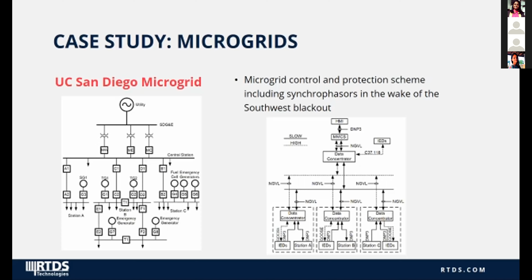On the left, you can see a diagram of the microgrid topology. You can see there are three utility ties, and this campus has the ability to split into multiple power islands. The microgrid control system has been designed to track all of these islands and make logical decisions based on the topology. This monitoring and controlling system has hundreds of devices consisting of controllers, protection relays, meters, and visualization tools. On the right, you can see the communication network diagram with both slow and fast moving protection and control data. Here, communication protocols include DNP3, IEC 61850 GOOSE, and synchrophasors, in addition to analog and digital outputs.